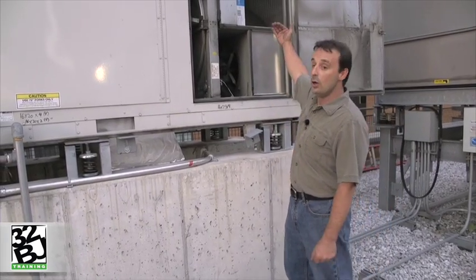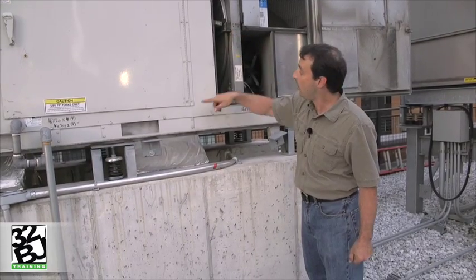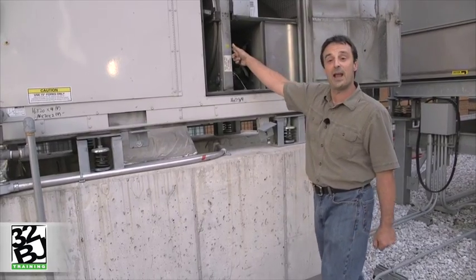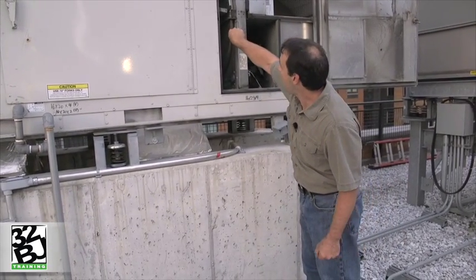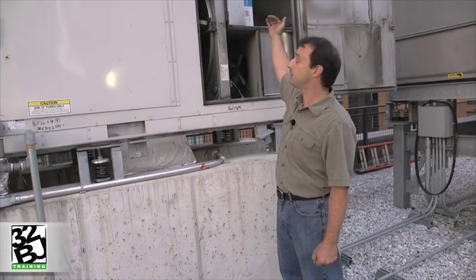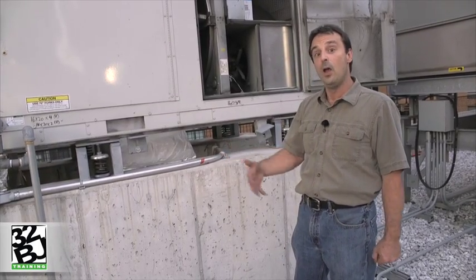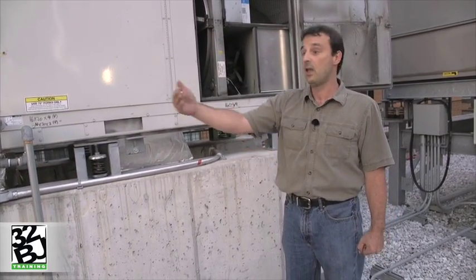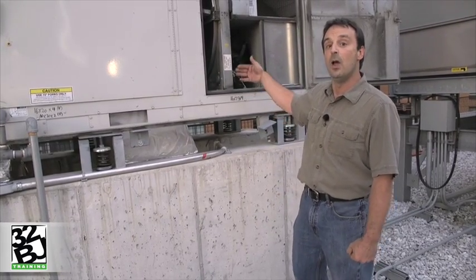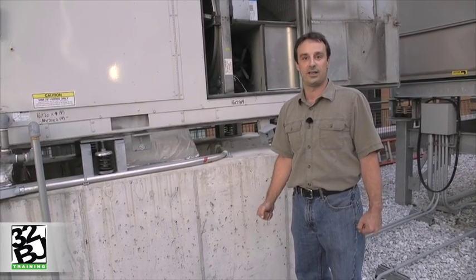In the wintertime, cool, dry air gets drawn in and passes through the enthalpy wheel. Warm, moist air is being exhausted and also passing through the enthalpy wheel. As it spins, that heat and moisture gets transferred to the incoming outside air. This helps to preheat that air, which reduces our energy costs on our gas furnace. In the summertime, the enthalpy wheel will pre-cool the air, giving us savings on our air conditioning system.